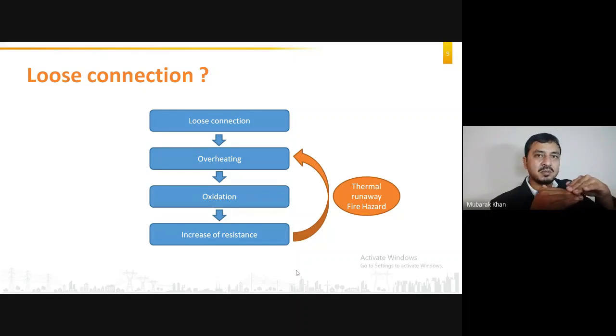Because of overheating, this bus bar, which is made of copper, right? In the presence of heat, which acts as a catalyst in the chemical reaction of copper with the atmosphere and other things available, which I showed 2 slides back, like ozone, nitrogen, etc. So heat becomes a catalyst. Under the presence of heat, copper oxide is formed at a faster rate. And as you know, the resistance of copper oxide is higher than copper itself. Because copper oxide is formed, the resistance will increase further. Because of the increase in resistance, there will be more heat. Because of more heat, more oxidation will occur. More oxidation will cause more increase in resistance, and it will become a closed loop where heat will keep increasing because of oxidation, and oxidation will cause the heating to increase.